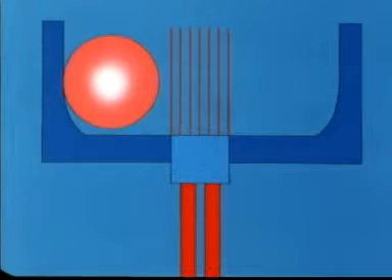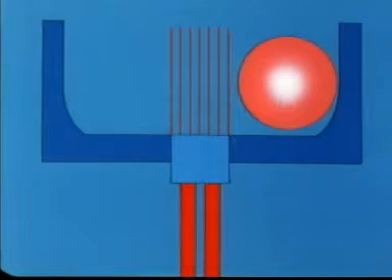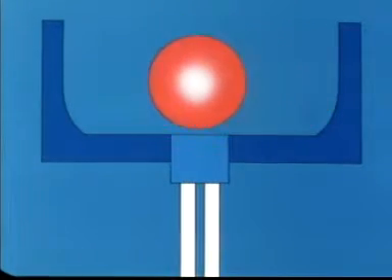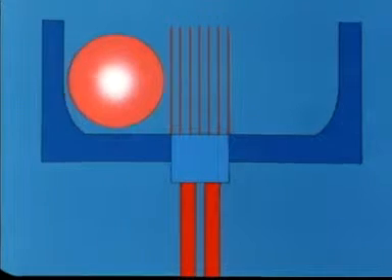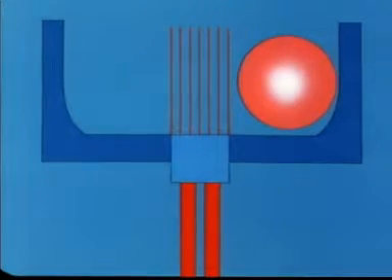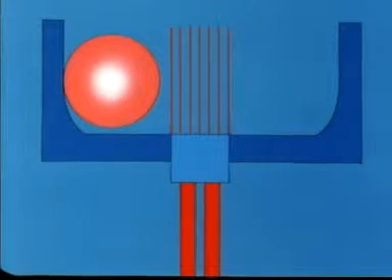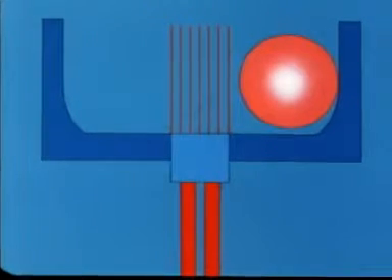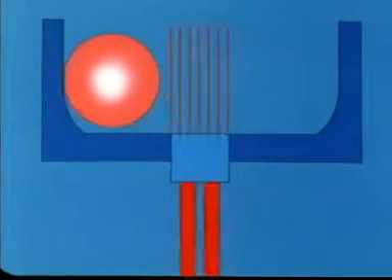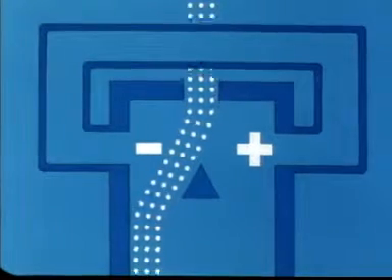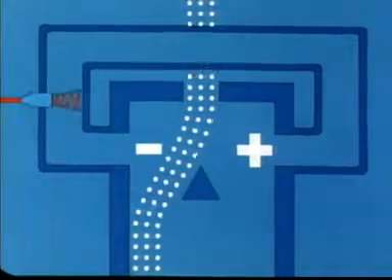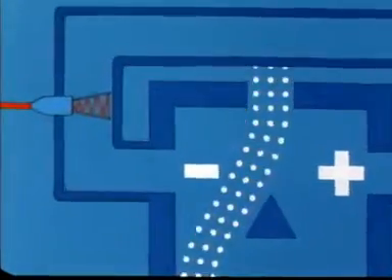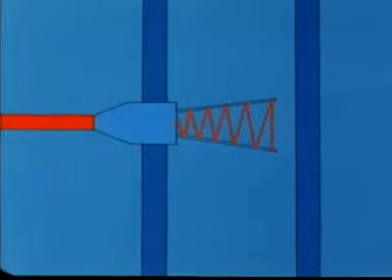We can count the pulses by electronically sensing the movements of the ball. Every time it changes position, the ball breaks an inductive field and an instrument records a pulse. This system is used for liquids. To measure gas flows, the pulse is provided by a thermal sensor in the interconnecting passage. Every control flow pulse through the interconnecting passage cools the sensor, and this is recorded as a pulse.